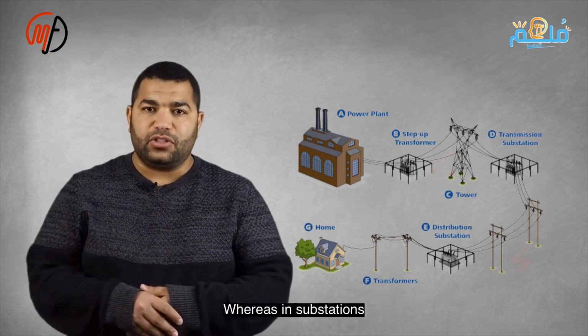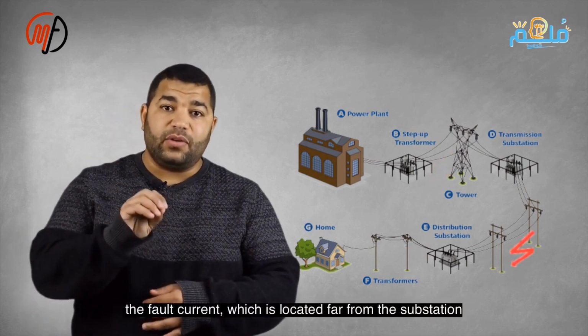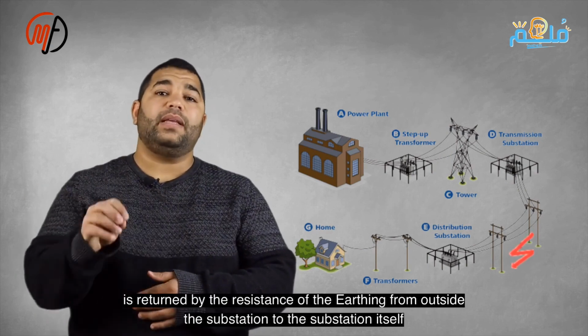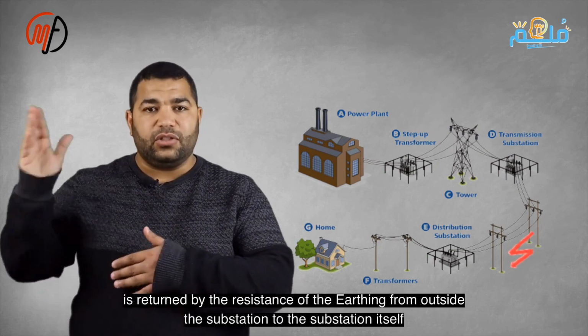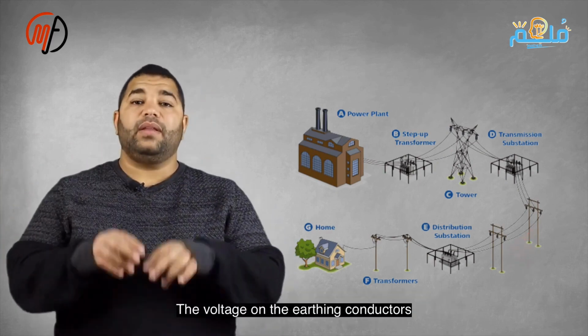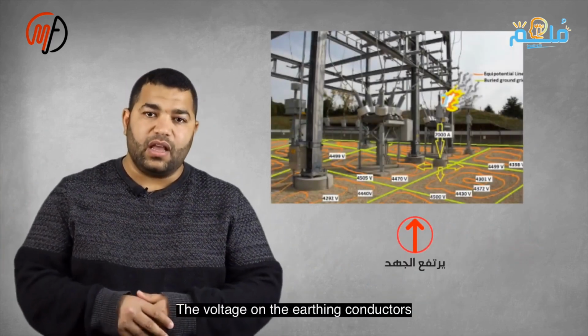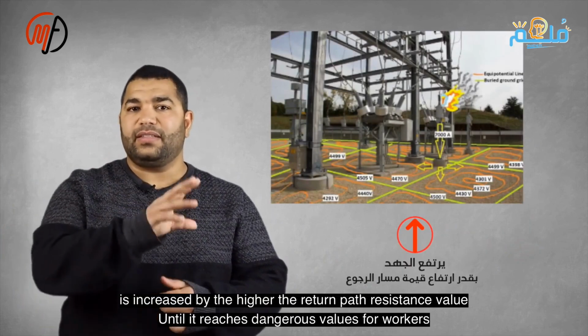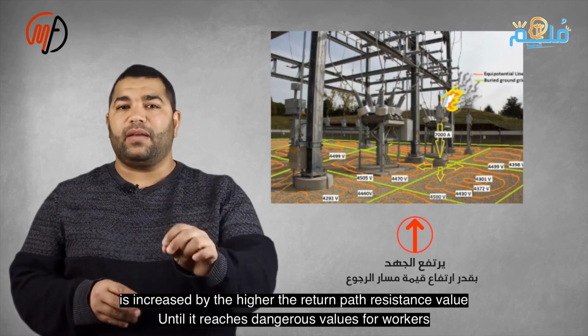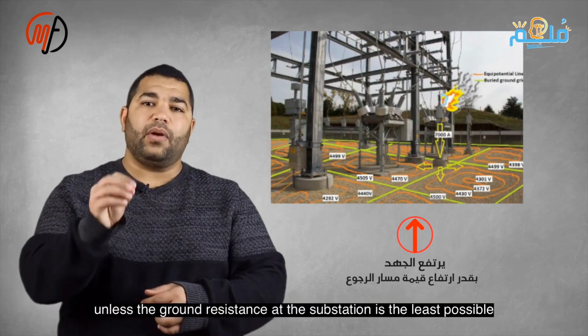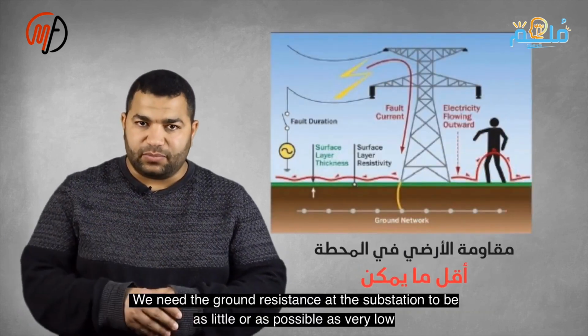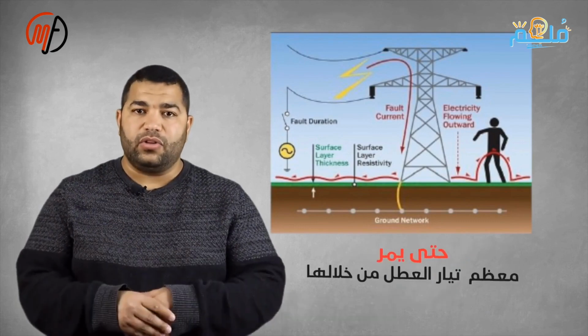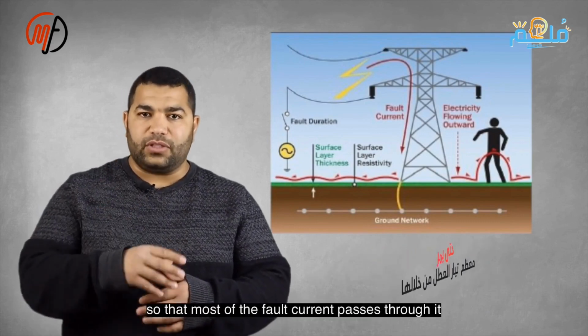In transmission stations, the fault current that occurs far from the station returns through the ground resistance, extending from outside the station to the station itself, causing the voltage on the conductors to rise according to the increase in the return path resistance, potentially reaching dangerous levels for the workers, unless the ground resistance in the station is kept as low as possible. We need the ground resistance to be as low as possible so that most of the fault current flows through it.